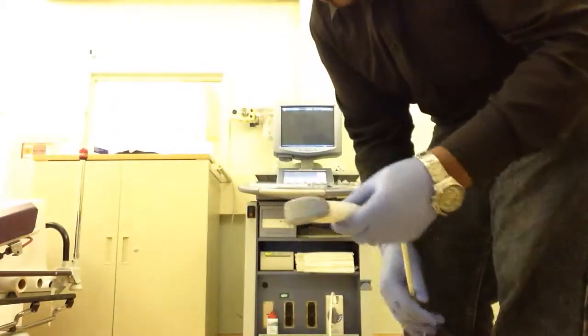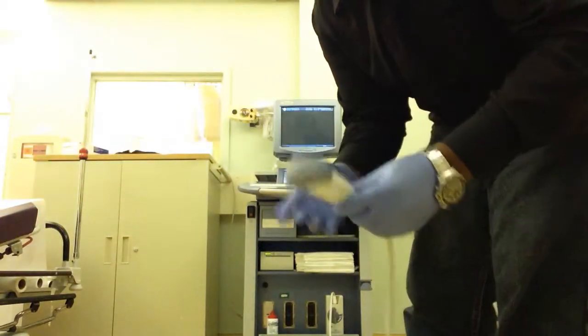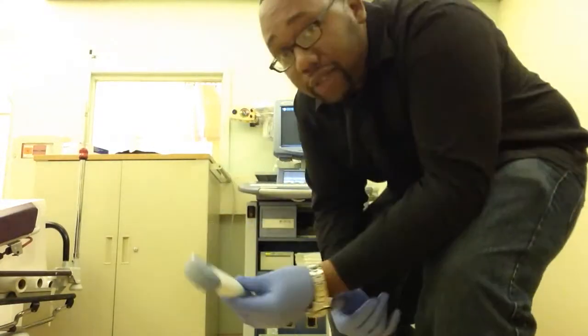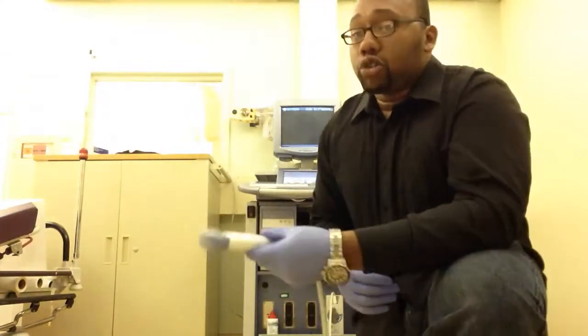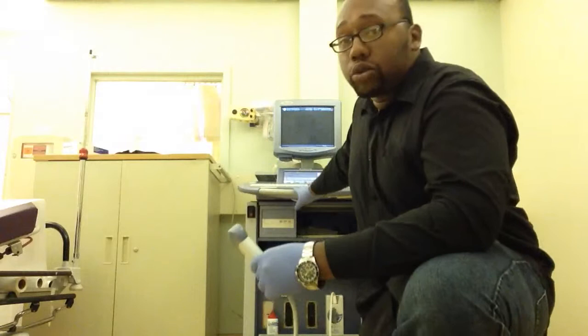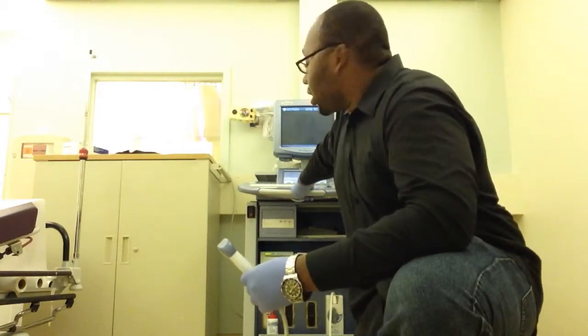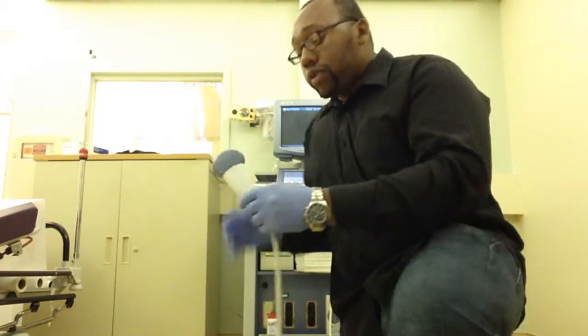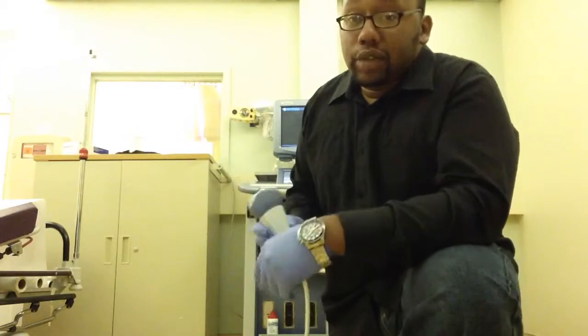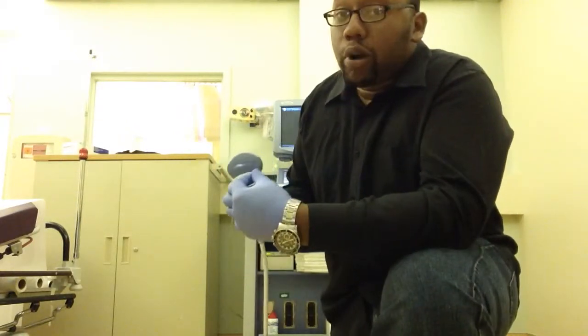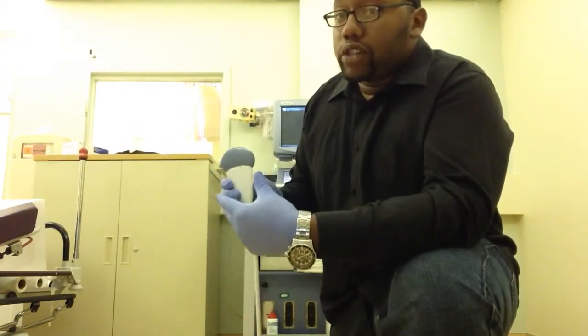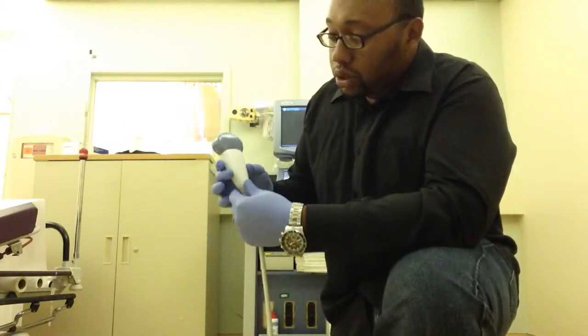First off, we're going to look at how we calibrate these transducers. That's what most of the calibrations have to deal with when we look at the ultrasound machine. Like I said, we really don't do any calibrations with the machine or the transducer itself. First off, let's look at the composition of the transducer. Now, I can't take this transducer apart, but we can try to give you a visual of what's inside.